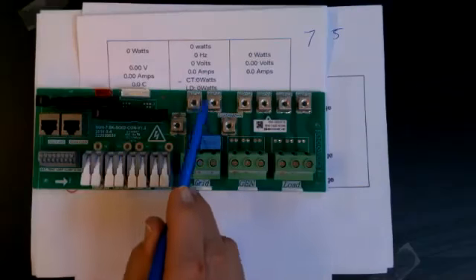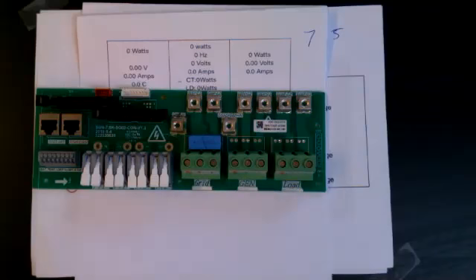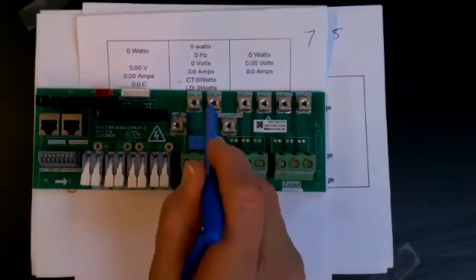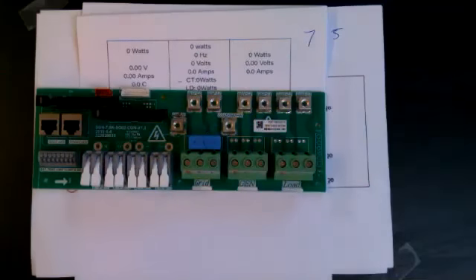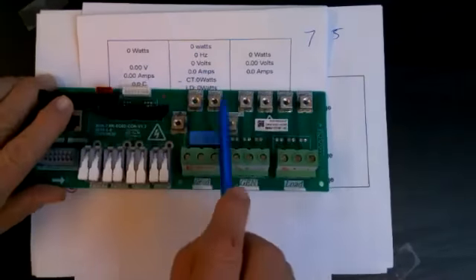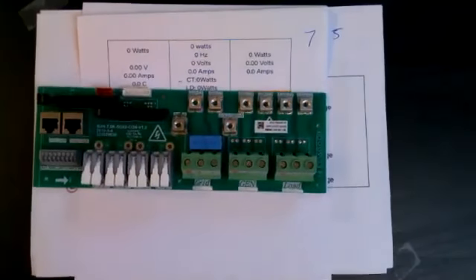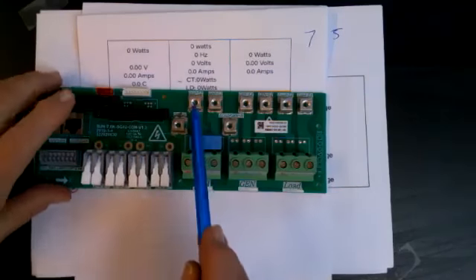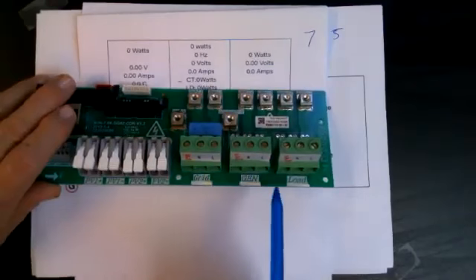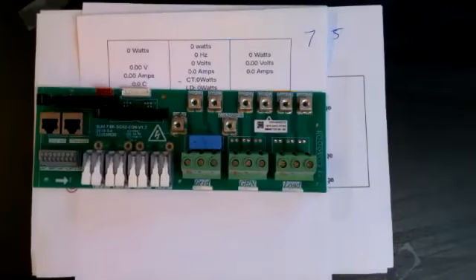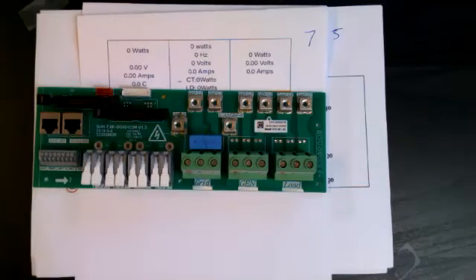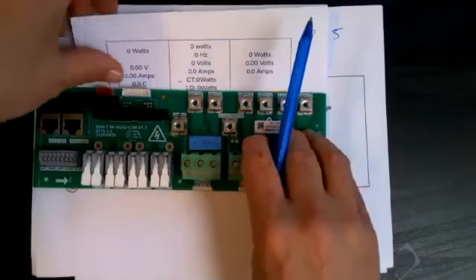Now, just before I go on, we have a few people mention questions. They often look at the wiring on here and they look at our internal wiring. And some people say, but we see marked negative or positive or whatever on the internal wiring. That doesn't matter. Always use the connections that are marked on here. There are some reasons why we change it around. Some people link the neutrals together, have a common neutral bus. And we had an issue in the past because we put our internal CT coil on the neutral. When they were linking out the neutral, it gave a problem because they bypassed our internal CT coil. So we swapped some of the wires around. It doesn't matter, that's just something that happens. So I point that out as a general comment.